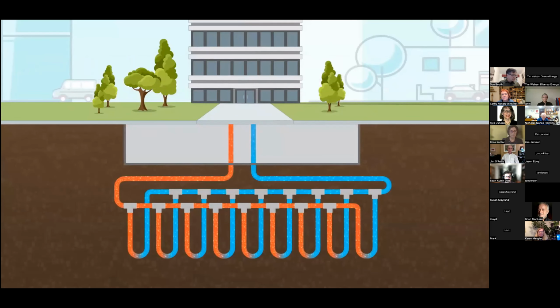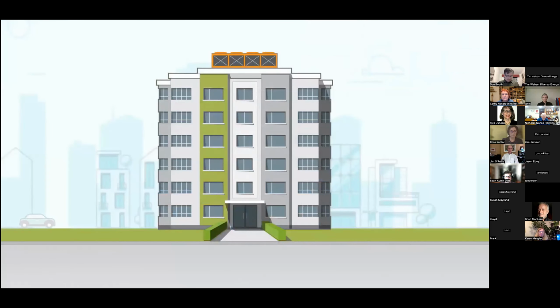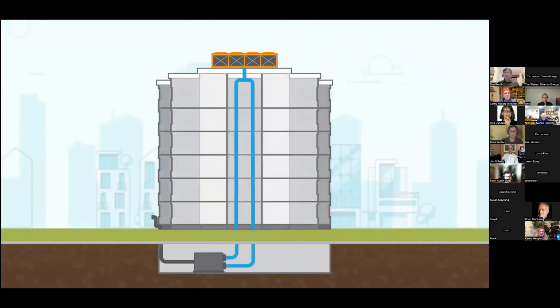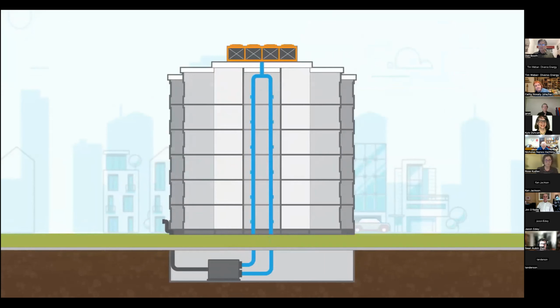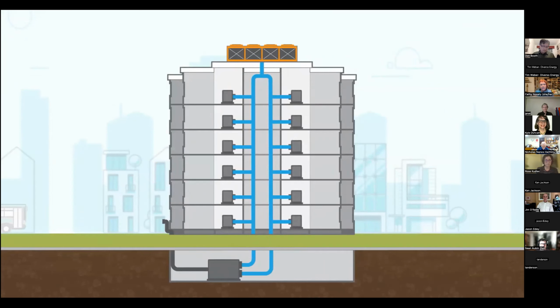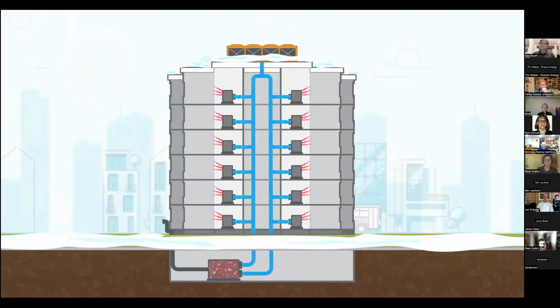To better understand how geothermal works, first let's look at the heating and cooling system of a typical building. Most multi-residential buildings have a central water loop which circulates throughout the building. This water loop is connected to heating and cooling equipment such as heat pumps. In the summer, heat pumps cool the suites and move the heat into the central water loop. From there, it is pumped to a cooling tower on the roof where it is rejected into the air. In the winter, the process is reversed, and the heat pumps warm the suites using the heat from the central water loop. To maintain a constant temperature, heat is injected into the loop by a boiler plant.